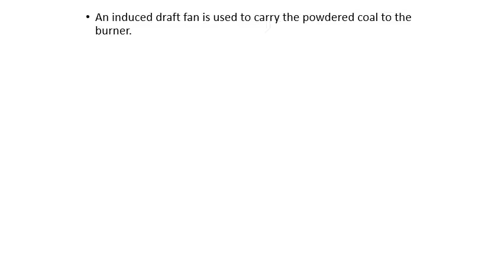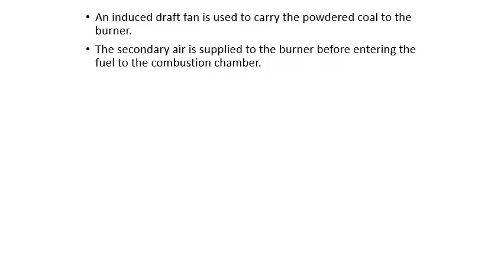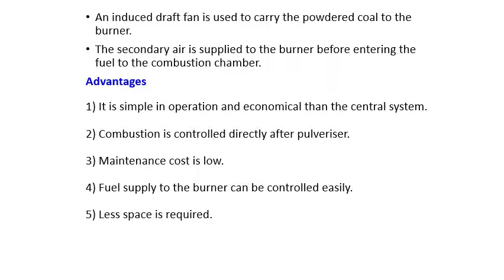The induced draft fan, or ID fan, is used to carry the powdered coal to the burner. The secondary air is separately supplied to meet complete combustion. The advantages are it is simple in operation and economical compared to the central system. The combustion is controlled directly after the pulverizer. Maintenance cost is less, and fuel supply to the burner can be controlled easily. Less space is required. And the disadvantages are it is very poor in handling variable load.